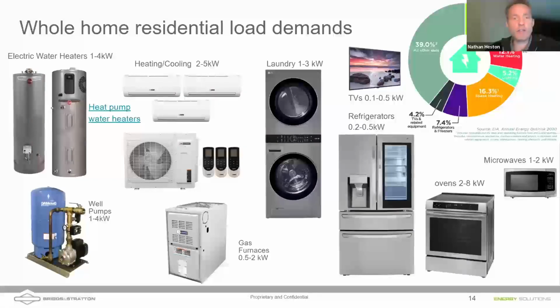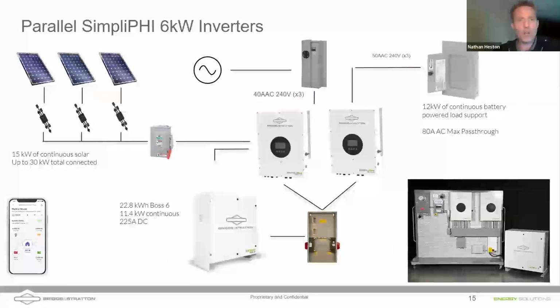So when you're educating your customers on the use of their backup system, their solar, their batteries, their inverter, it's worth pointing out to them the different devices that can cause overloads and the different devices that, when being used, are really demanding. So I wanted to show what it would look like if we wanted to parallel a couple of 6 kilowatt inverters. We're still going to need a critical load backup.